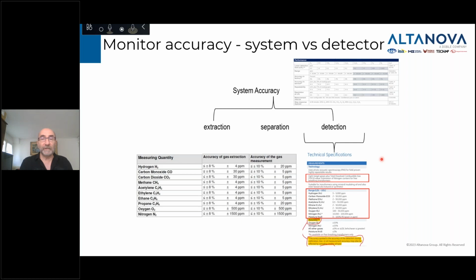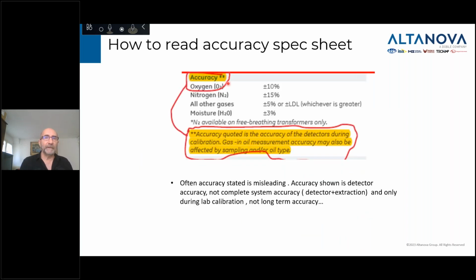Another way to do it is that people will specifically just show the detection accuracy. So they will tell you that your accuracy is plus or minus 5%, but it's just the detector during calibration. Now, calibration usually happens in the factory. So what it means in general is that my system detector accuracy, when I calibrate it before shipping, is 5%. But it's not my system. My system is higher than 5%. Is it 10%, 15%, 20%?